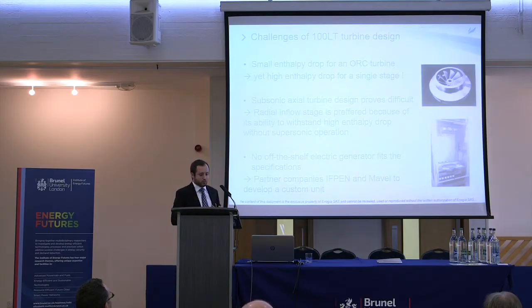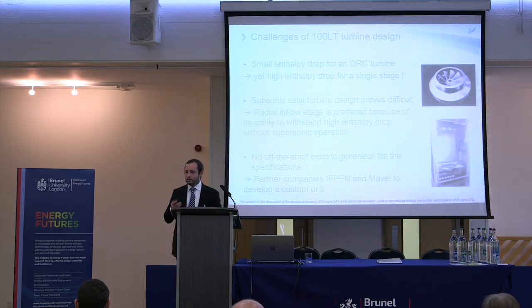So we worked on a new turbine design, called the 100 LT for low temperature. At low temperature, it's a small enthalpy drop for an ORC turbine, but a high enthalpy drop for a single stage. So we chose a radial stage because it gives us a subsonic turbine with this enthalpy drop, and the efficiency is very good.